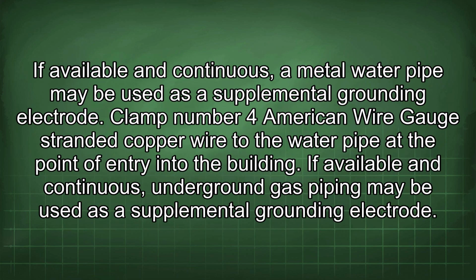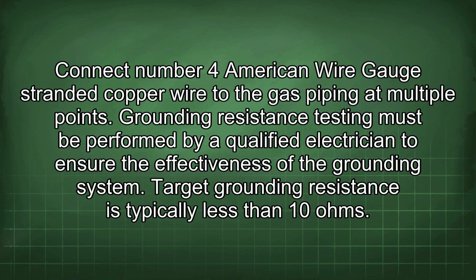If available and continuous, a metal water pipe may be used as a supplemental grounding electrode. Clamp number 4 American wire gauge stranded copper wire to the water pipe at the point of entry into the building. If available and continuous, underground gas piping may be used as a supplemental grounding electrode. Connect number 4 American wire gauge stranded copper wire to the gas piping at multiple points.